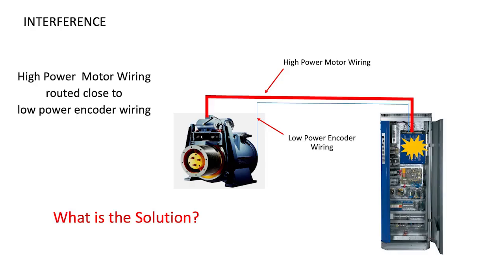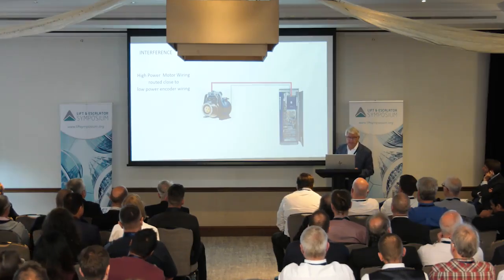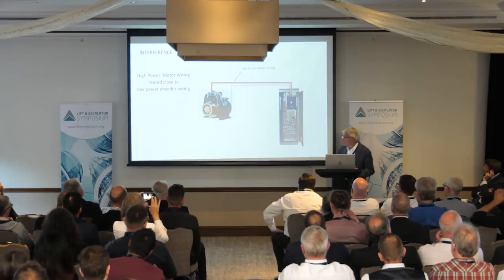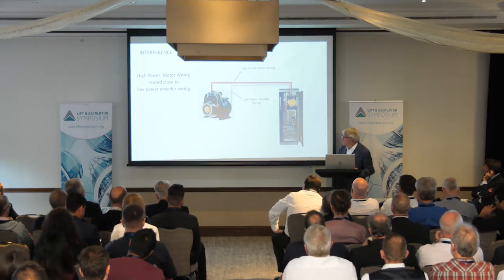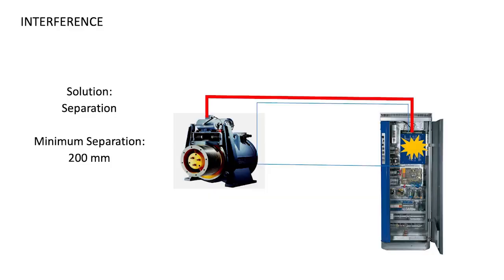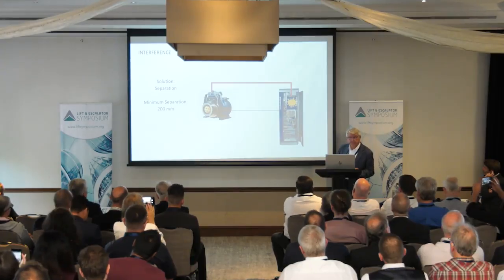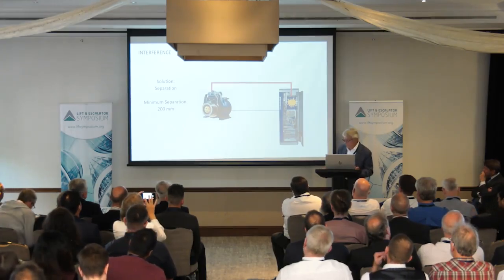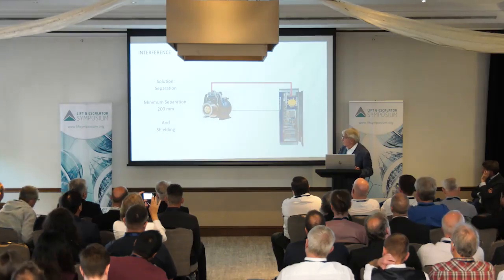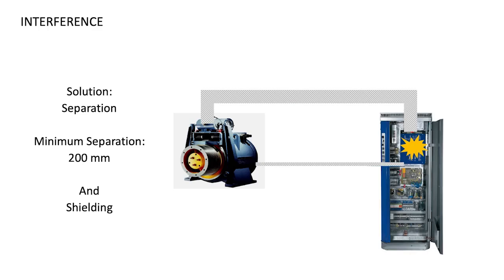Let's look at some practical examples. Here we have a machine and a drive, and we've routed the encoder wiring next to the power wiring to the motor. That's a good way to induce or couple interference into the system. So what can you do in a situation like this, where the drive is making noise? The solution is separation - reroute the wires further apart. That works, and the minimum separation is 200 millimeters, though further is better. You can also add shielding, which is the best solution, putting them in conduits or troughing that's earthed, greatly reducing or eliminating the problem.